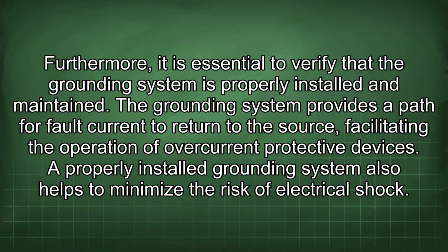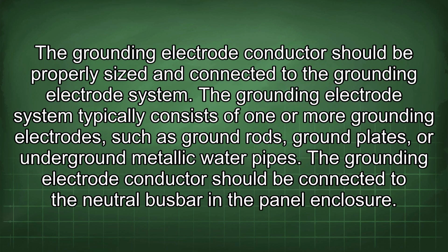Furthermore, it is essential to verify that the grounding system is properly installed and maintained. The grounding system provides a path for fault current to return to the source, facilitating the operation of overcurrent protective devices. A properly installed grounding system also helps to minimize the risk of electrical shock. The grounding electrode conductor should be properly sized and connected to the grounding electrode system. The grounding electrode system typically consists of one or more grounding electrodes such as ground rods, ground plates, or underground metallic water pipes. The grounding electrode conductor should be connected to the neutral busbar in the panel enclosure.